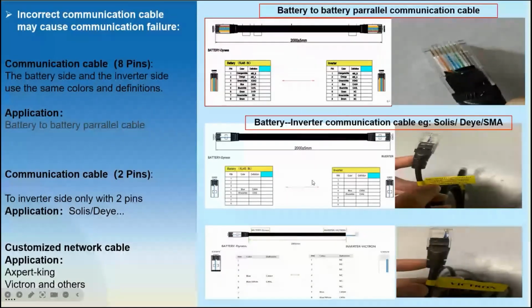And some other inverters may use a customized communication cable, such as Victron. This is the Victron communication cable, and its label is marked Victron, and the other side is marked inverter. So you use this side for the inverter, and the other side is marked battery. If you compare this cable with the other one, the definition is actually different. Although on the battery side they both use blue and blue white, on the inverter side they use a different definition. They use pin 7 and pin 8.